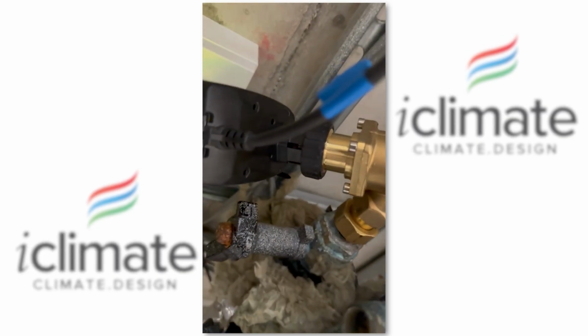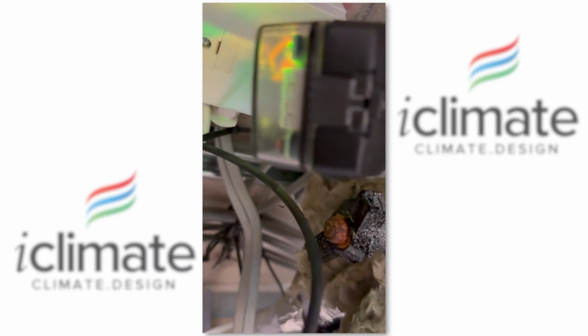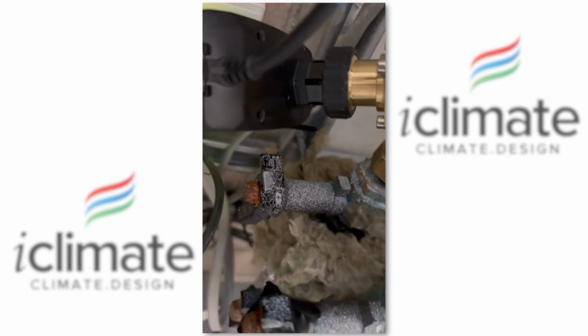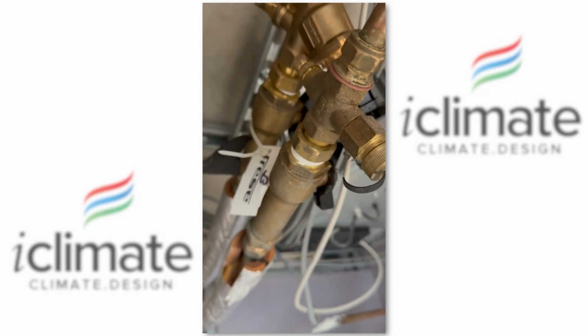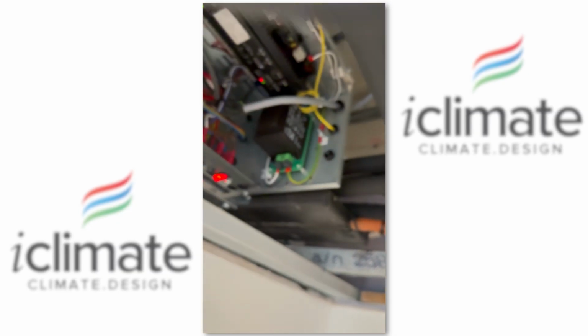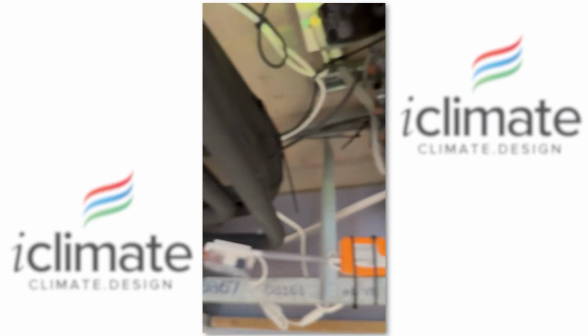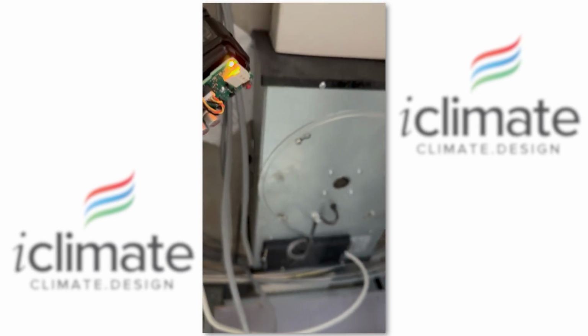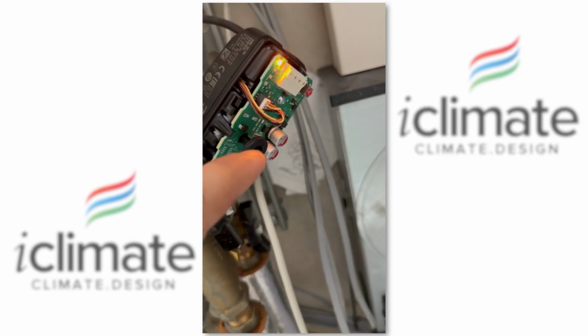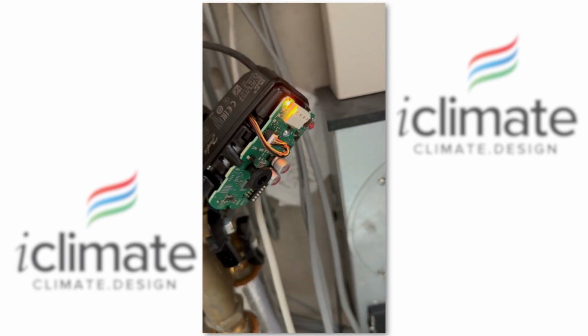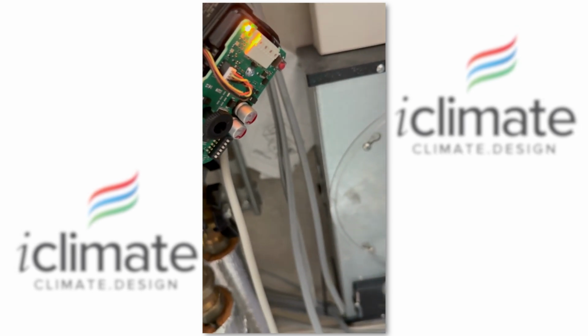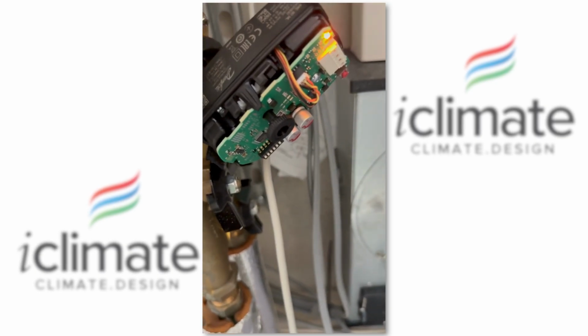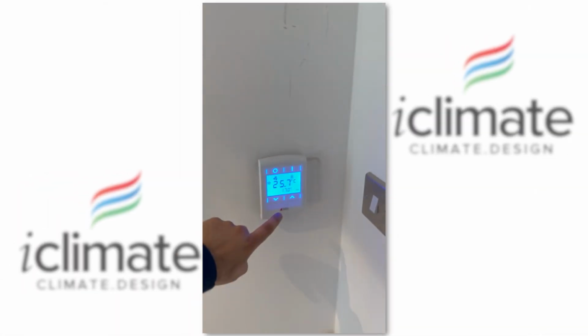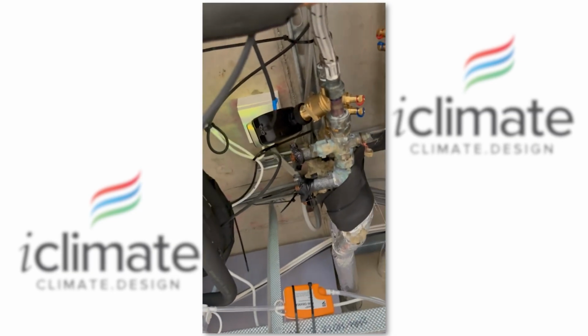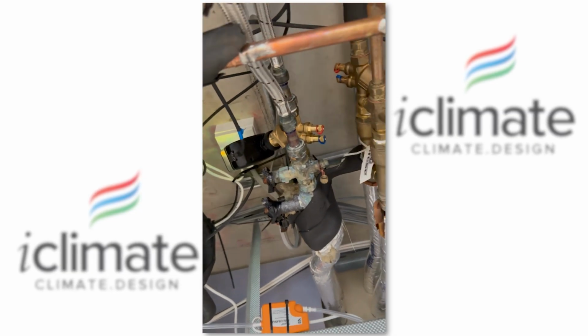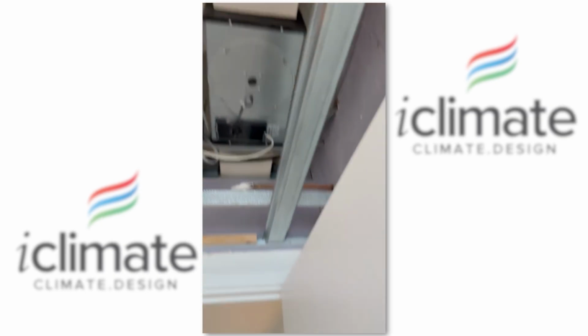We found there was too much flow coming down here. The light indicating orange shows that the cooling valve is active. The bottom pipe is flow, lovely and chilled. The top pipe is coming back a bit warm. This is the heating valve and shows you the inside of the actuator. That means that position is fully closed. The valve has been given its signal, and when I adjust the heating, you will see that actuator will move. Now the unit is doing its cooling, the actuator valve is stepped down, stepped back up. We have decent airflow and water coming out.